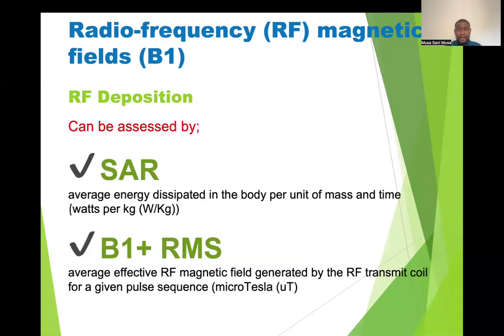So still talking about the RF coil, there are two things that we need to keep in mind in order not to expose our patients to an unacceptable level of RF deposition. We have to be careful or monitor our specific absorption rate. Like we said, the average energy deposited into the body per unit mass, which is usually in watts per kg. And for the majority of implants, the whole body maximum RF deposited energy is less than 2 watts per kg.